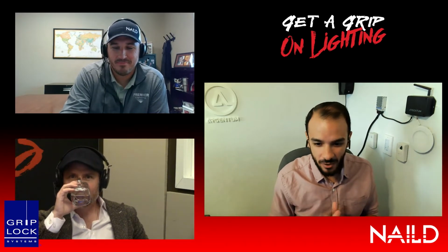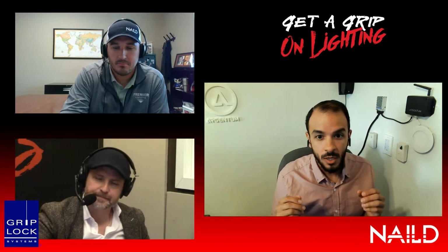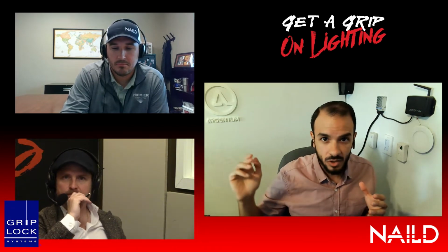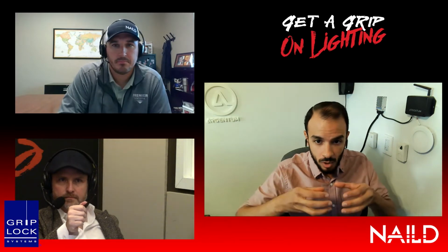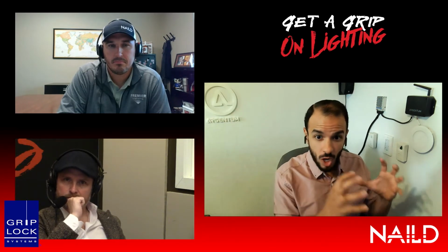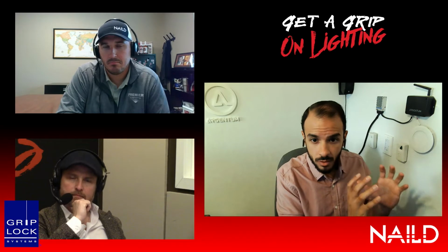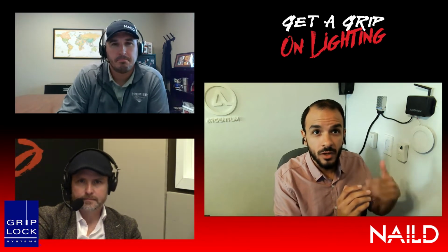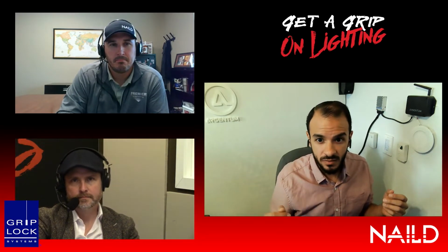In a regular LED fixture, you have many LED fixtures each with their own rectifier on a smaller scale, and the economics don't work to make that high efficiency. But if you have one giant rectifier, only one for every floor of the building, where every lighting panel has one giant rectifier, the economics work so you can make it 99% efficient, with very low heat and very low losses, because you only have one of them and space is not really a constraint.